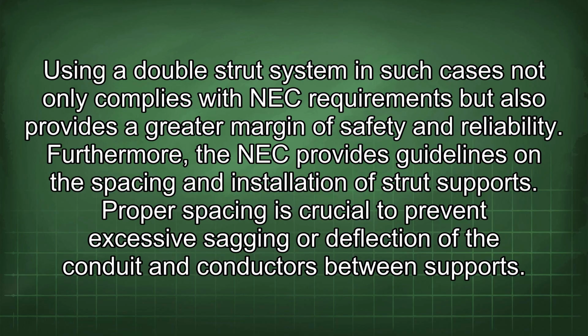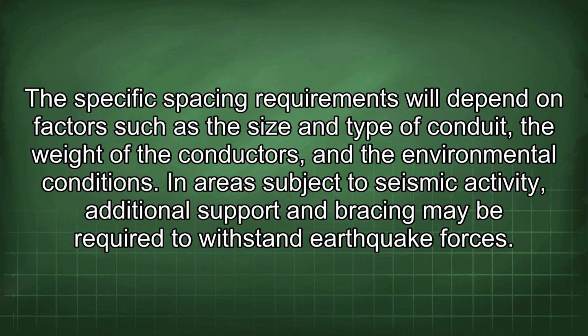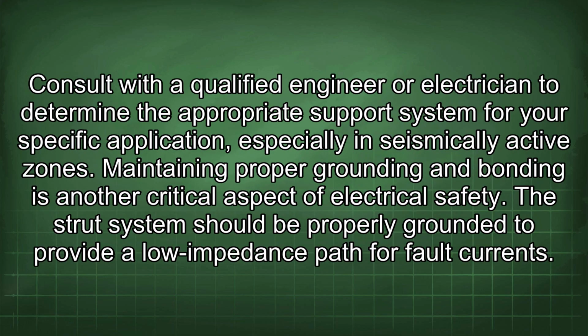Furthermore, the NEC provides guidelines on the spacing and installation of strut supports. Proper spacing is crucial to prevent excessive sagging or deflection of the conduit and conductors between supports. The specific spacing requirements will depend on factors such as the size and type of conduit, the weight of the conductors, and the environmental conditions. In areas subject to seismic activity, additional support and bracing may be required to withstand earthquake forces. Consult with a qualified engineer or electrician to determine the appropriate support system for your specific application, especially in seismically active zones.